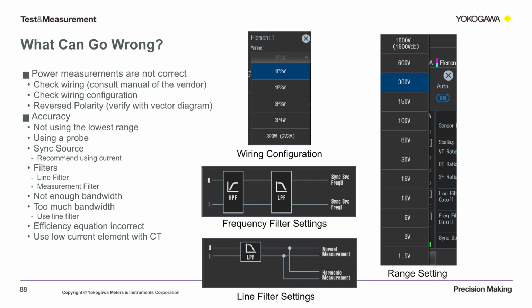If you're using a probe, those are not going to be the most accurate ways to bring in voltage and current. You might want to use a more direct source. You also want to check your sync source. Sometimes if you're using voltage for your sync, it could be noisy, so we recommend using current. Also, there are settings for your frequency filter and your line filter that can clean up both your measurements as well as your synchronization. If there's not enough bandwidth, you'll need to know your fundamental frequency, and you might need a new instrument. But if you have too much bandwidth, you might want to use a filter.